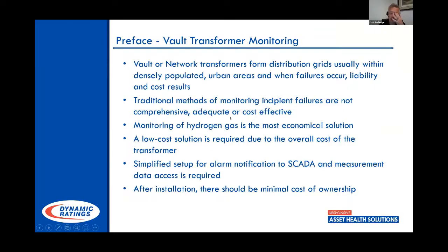So just to quickly preface, just to go over what these are for those of you that don't know. Network transformers are typically located in your downtown areas and larger cities to mid-sized cities, and it's really a means of having improved reliability for that part of town. So you can have multiple circuits coming out of your substation that are feeding 3 or 4 or 5 transformers in a vault. So that particular grid is being supplied by multiple distribution circuits coming from your station. Therefore, losing a single circuit doesn't really affect the reliability of that network. So these vault or network transformers form these grids, and typically, if you walk over grates downtown, you'll see them. They're located in underground vaults. Occasionally, they're located in a walk-in vault in the basement of a building.